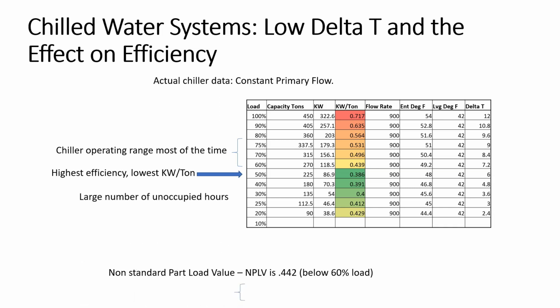Then we start looking at unoccupied. You have very low load, but you're running 24/7 on this chiller, and so its efficiency on low load is not so good also in comparison to its most efficient operating point. And there your low delta Ts are showing up. You have a constant flow on the primary of 900 GPM, and you're getting down into the 3.6, 3 degrees, and 2.4 degree range. That's where your efficiency goes down. It takes more energy to maintain this low load than is practical.